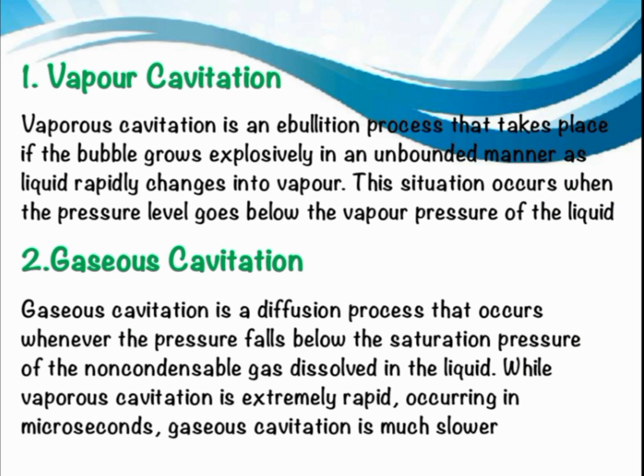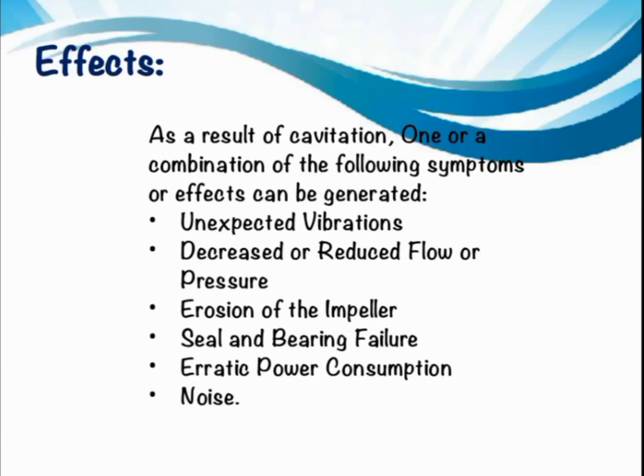Second, gaseous cavitation. Gaseous cavitation is a diffusion process that occurs whenever the pressure falls below the saturation pressure of the non-condensable gas dissolved in the liquid. While vaporous cavitation is extremely rapid, occurring in microseconds, gaseous cavitation is much slower.